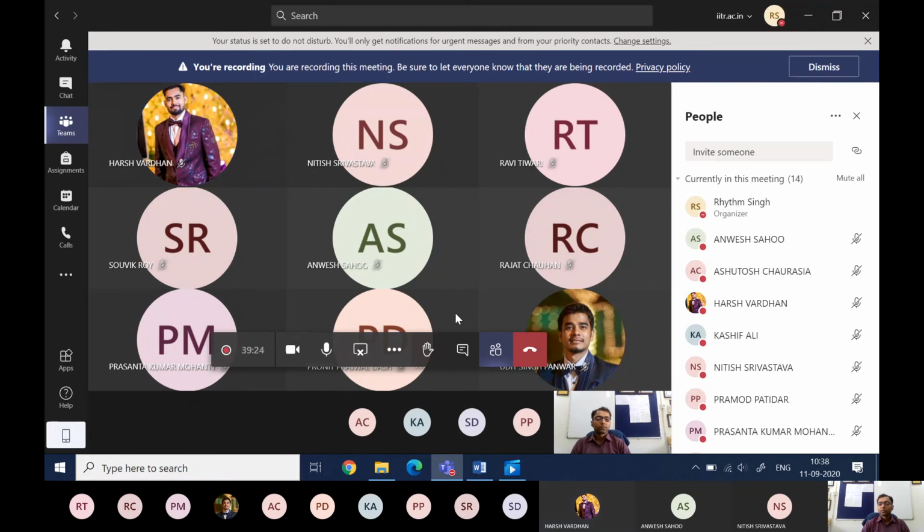Okay, anyone else? Any question? Okay, sir, so the torque angle. Torque angle we discussed. You remember the delta, that phasor diagram we made. So V phi and EA. So the angle between V phi and EA, that was the torque angle or the internal angle. That should be in 20 to 30 degrees. Right. Okay, sir. And anyone else? Any other question? Or any inputs in this?